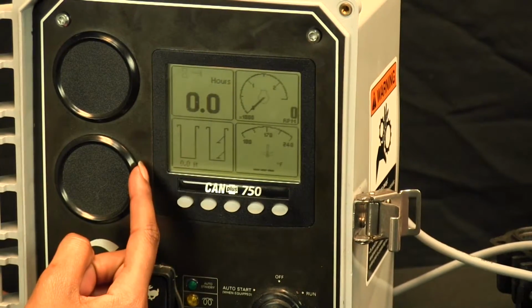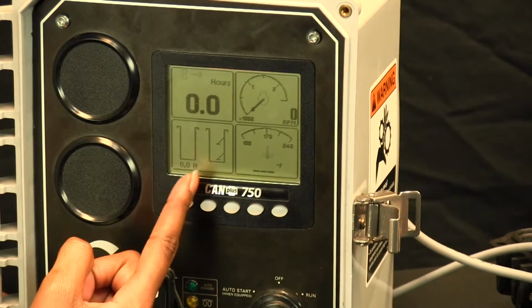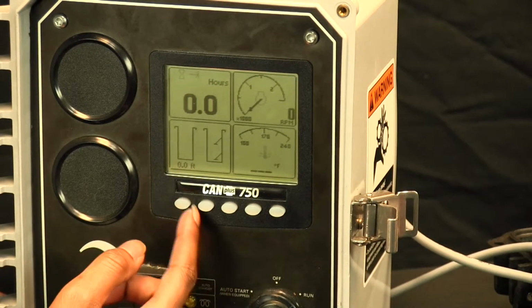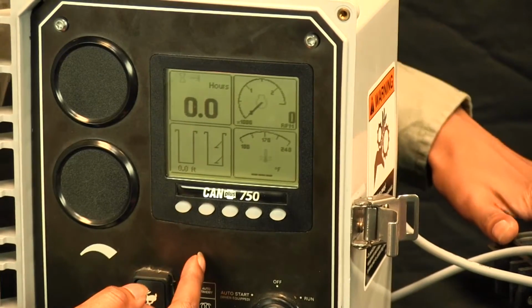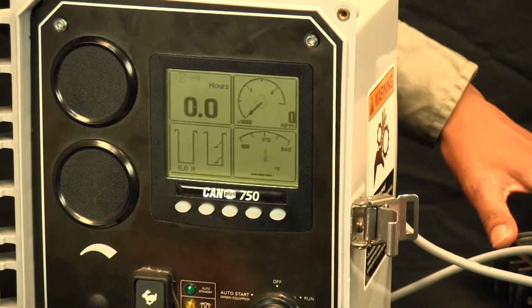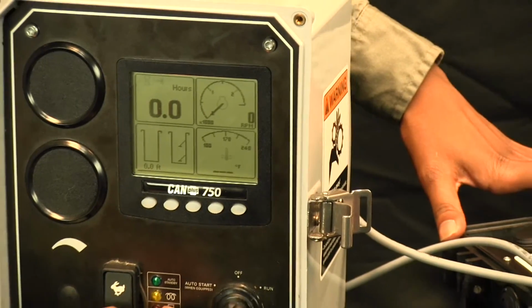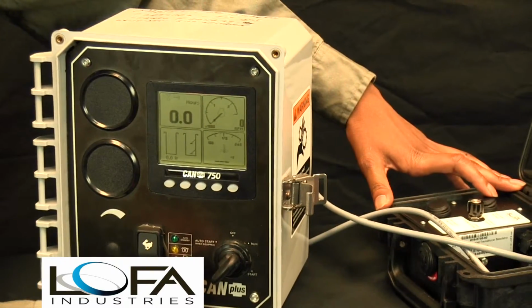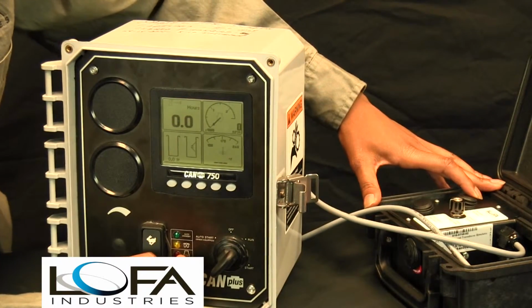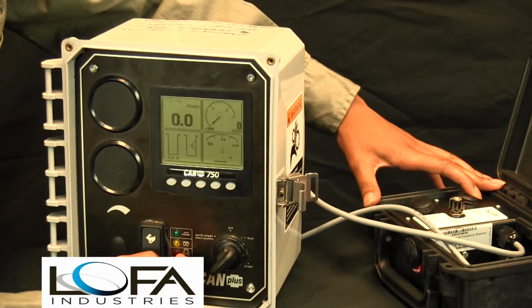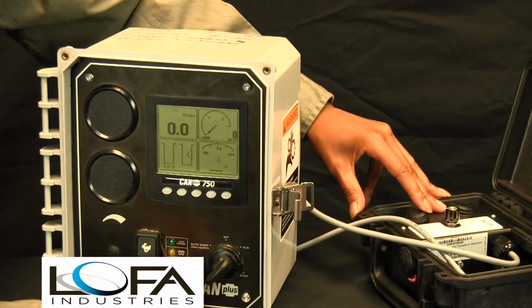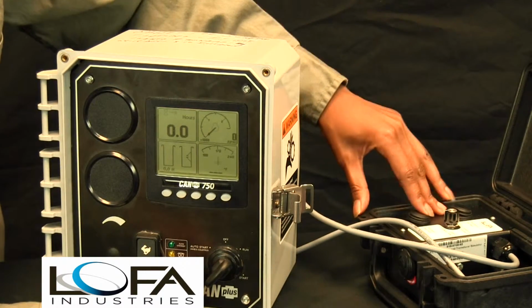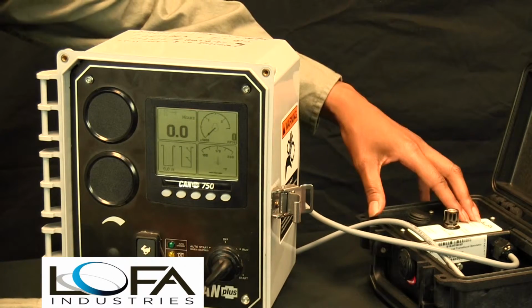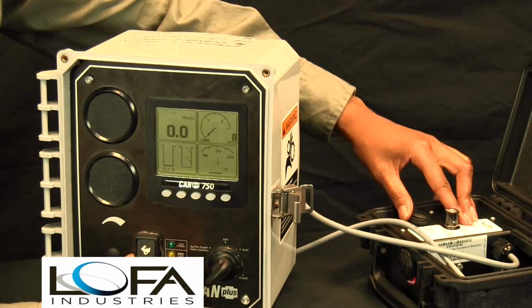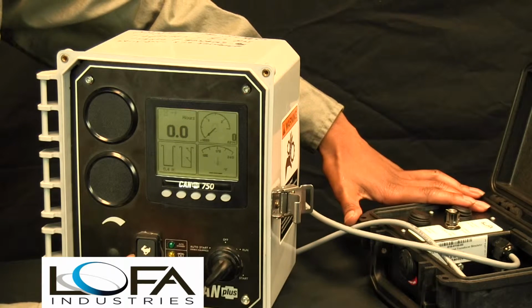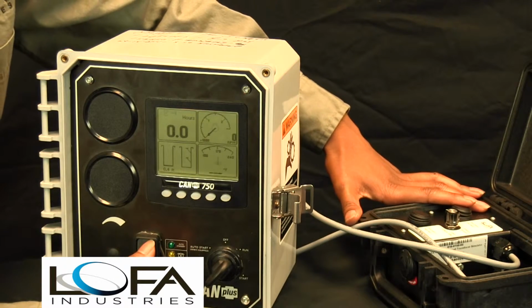There's going to be two containers, one with two swinging arms and then an empty one. So let's just say you have a dual float operation, and let's close the first float, the low float, and this is what it would look like. You should see that bottom arm swing up. That means that it's closed. Now let's close switch 2 or float 2. And that's how it would look on the displays. So say for instance, if you had a dual switch empty, that would create a start event.